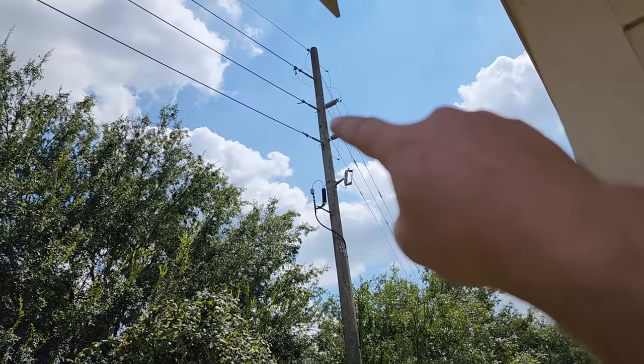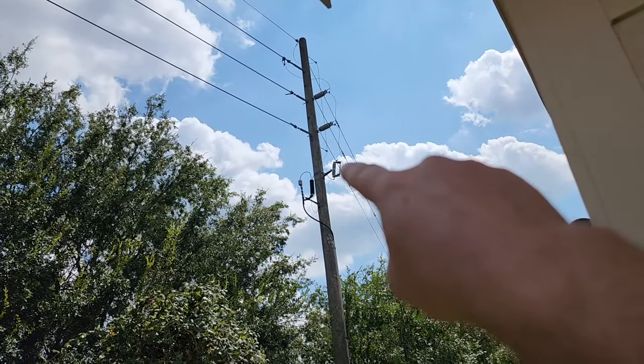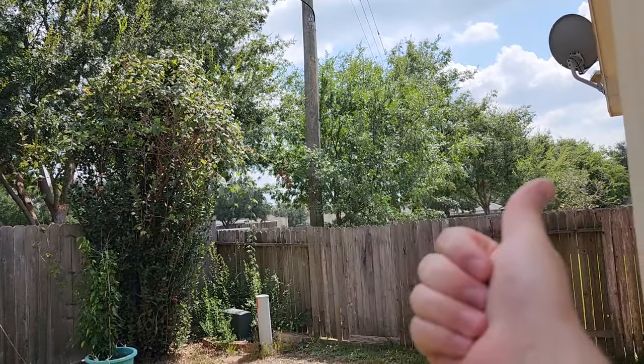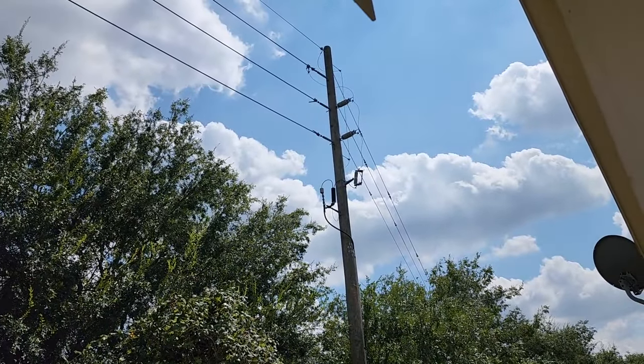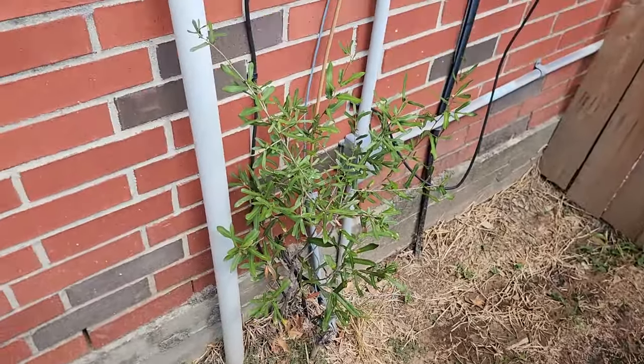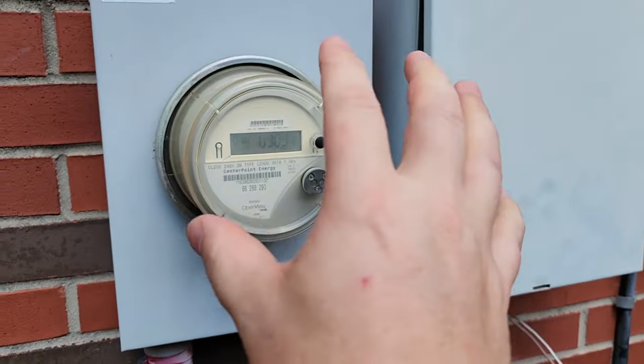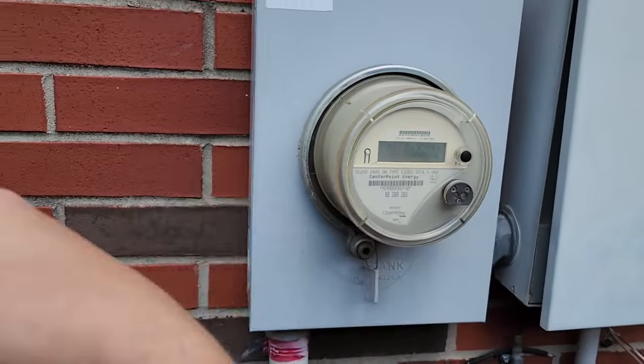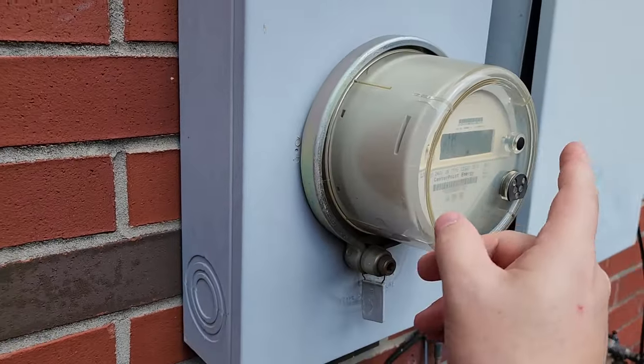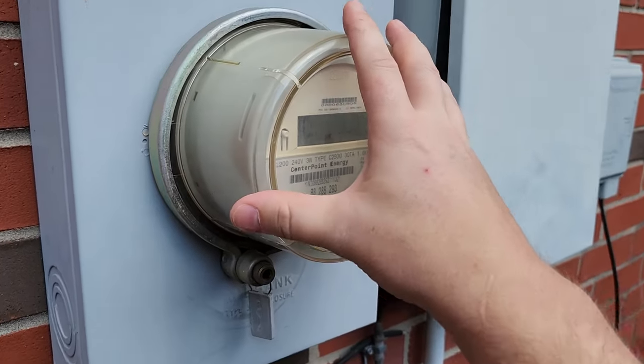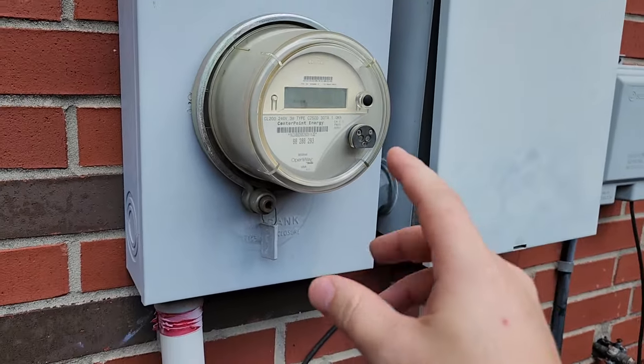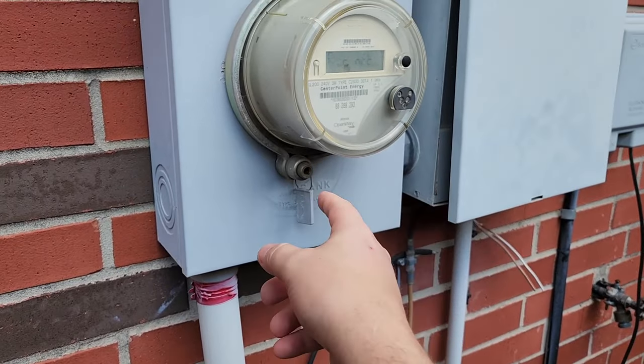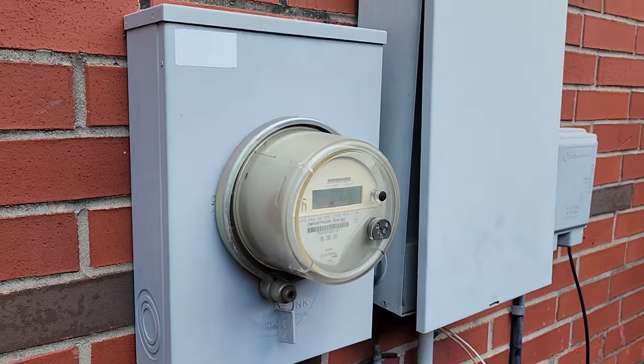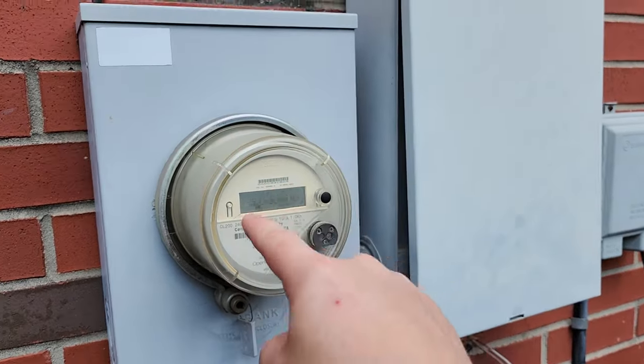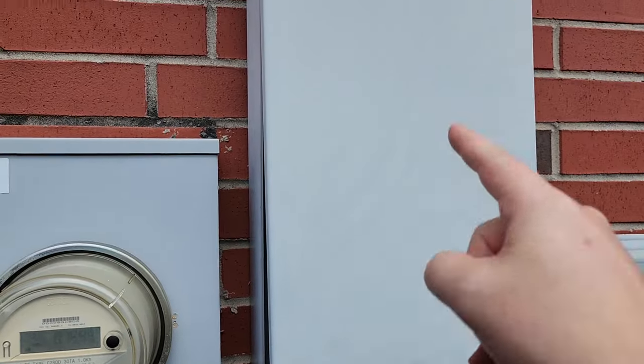So right here, you can see that one of my phases is tapped off. It goes through a fuse right here, comes down to my transformer, and then it goes over to my panel. So let's go ahead and take a look over at the panel when it's already at the 220 volts. The power comes off the step-down transformer up here into the meter, and the meter acts not only as a metering device to get back to the invoicing company so that they know how much they're going to charge you, but your meter is also a service disconnect. So if you don't pay your electric bill, they will pull your meter out and put in a blocker plate, and the blocker plate prevents electricity from going over here to here.